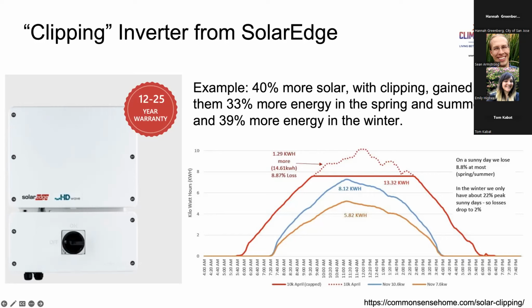So in this case, they have 40% more solar installed with a clipping inverter. From 7.6 up to 10.6, that's 40% more. And then they got 33% more energy in the summertime, spring and summer. And they got 39% more energy in the wintertime.